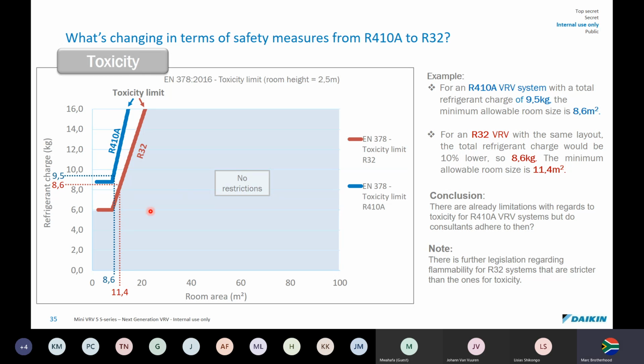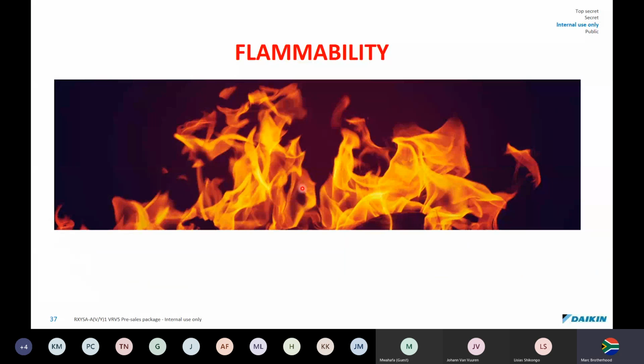So now you can have a bigger room area if you go R32. If I take 8.6 kilograms across because it uses 10% less and I drop that down, I see that my room size can go up to 11.4 meters squared. Right, this is what everybody panics about, is the flammability.